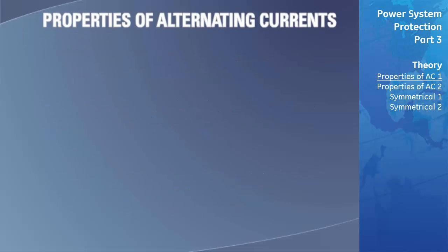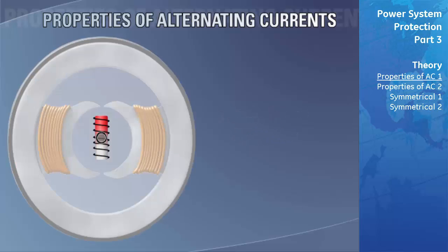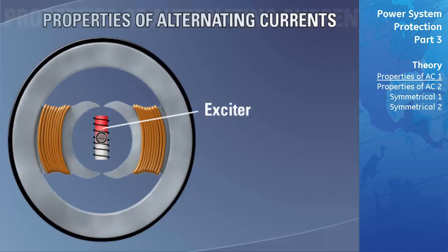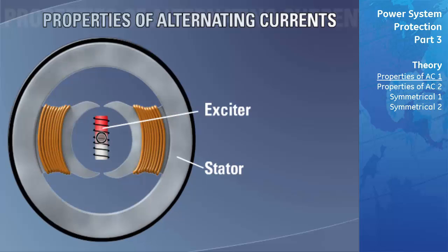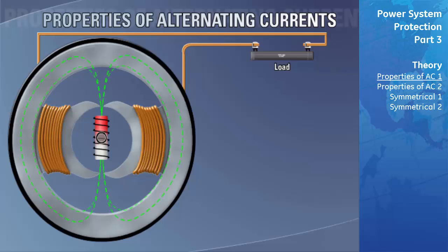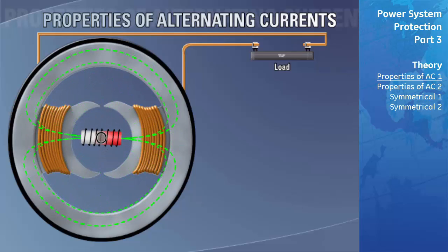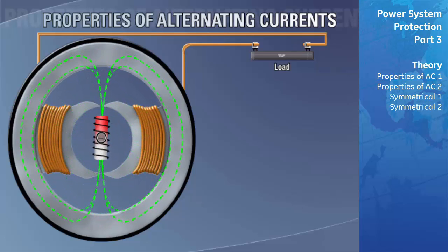For instructional purposes, let's look at the theory of operation of a single-phase electrical generator. The single-phase generator is composed of two major components: the exciter and a stator. The exciter is an electromagnet that rotates about its axis. The stator is constructed from two electromagnets or poles wired in series with a load and remains stationary. When DC current flows through the exciter windings, a magnetic field is formed, and as the exciter rotates, its field cuts through the stator windings, inducing a voltage.